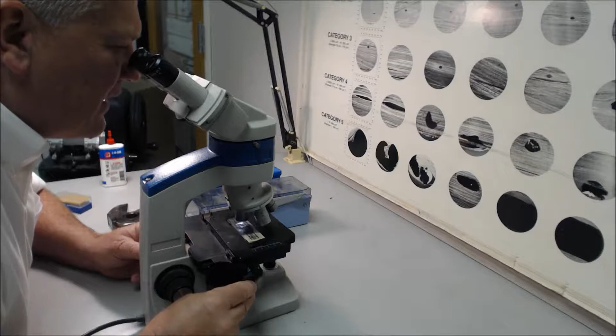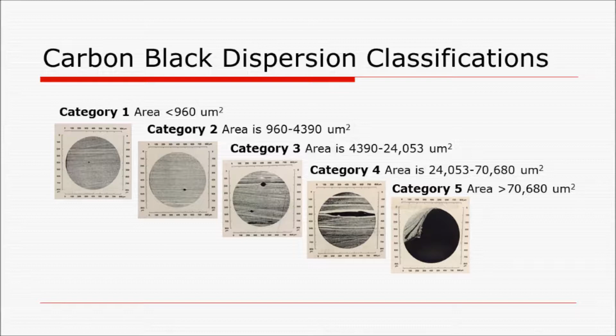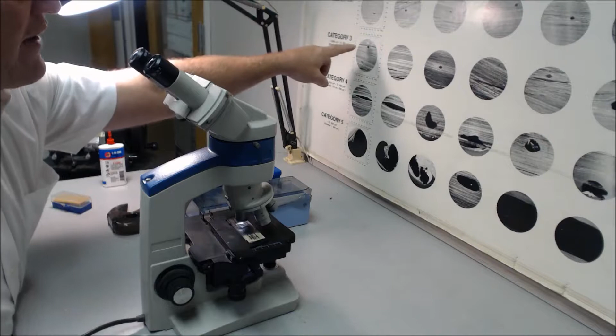This particular reticle on the left hand side has the calibration in it, and what you do is you focus in on the 2 different fields of view and then you categorize it. These categories are described 1 through 5 in the ASTM chart. You categorize them by agglomerates. These are typically spherical agglomerates of known area, and you use the calibrated reticle to judge that. You have 10 different views. You average those 10 views to the nearest 10th, and that's how the test is conducted.